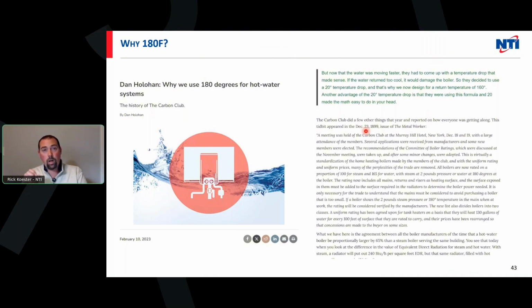So they started to develop a pump. In this case, it wasn't a circulator; it was a pump called a booster pump, and B&G developed it. And what happened now is at 212 degrees, you put that pump on and push that water out. All that cold water that came back to the boiler would shock that boiler and crack it. So they had to develop a temperature that was less than boiling, all right? So they picked 180 degrees. That's exactly where they got 180.